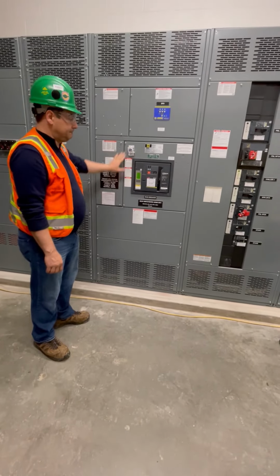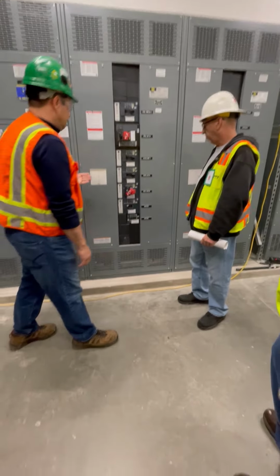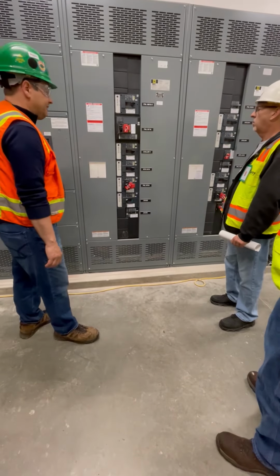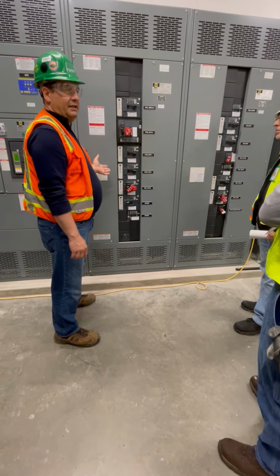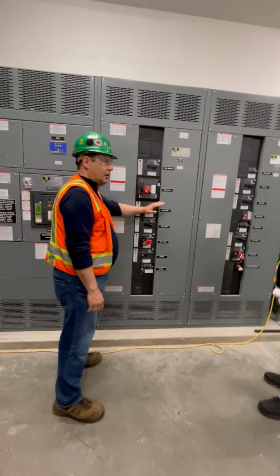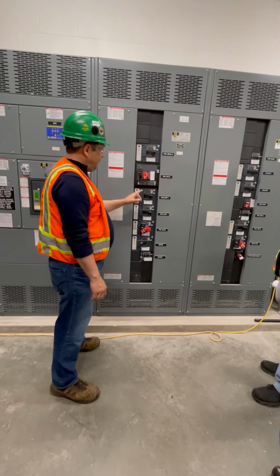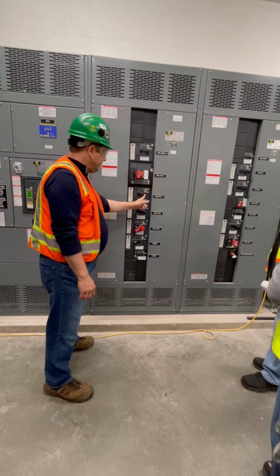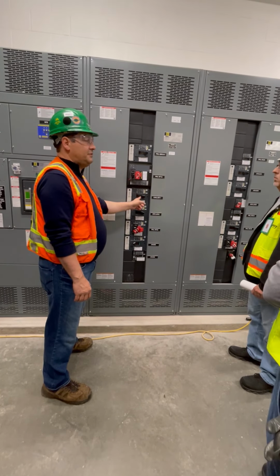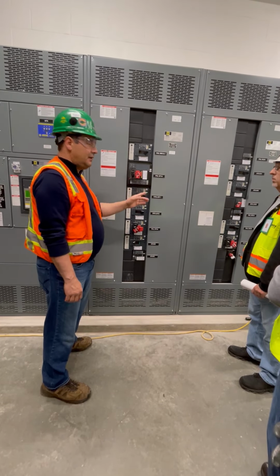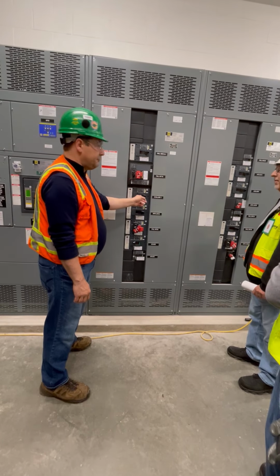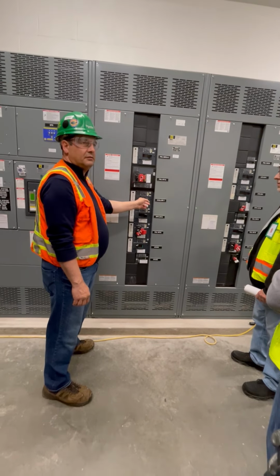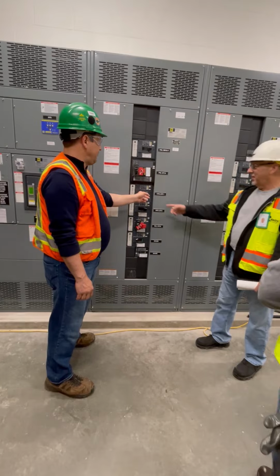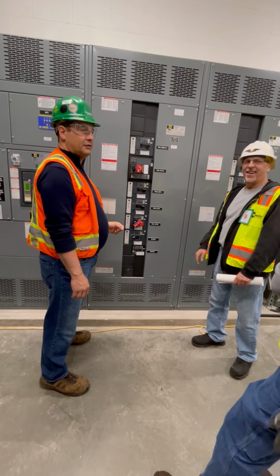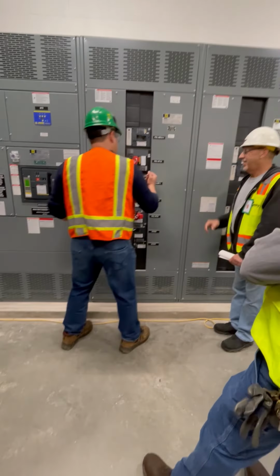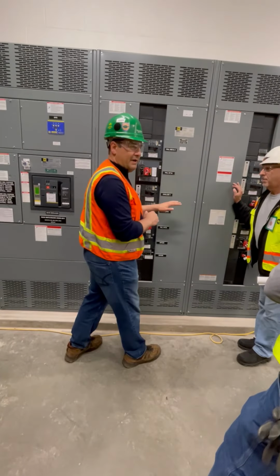Makes sense. Okay. In difference to this breaker, you don't have to charge the mechanism on, off. But if the breaker trips, the handle will be, sometimes it's kind of misleading in a way. It will trip, it will be just half an inch or something lower from where it is right now. See that little gap in between? And you do have to reset it before you turn it back on.